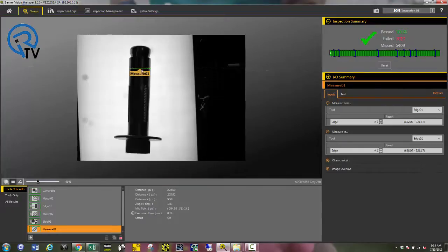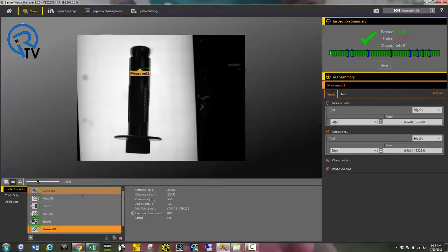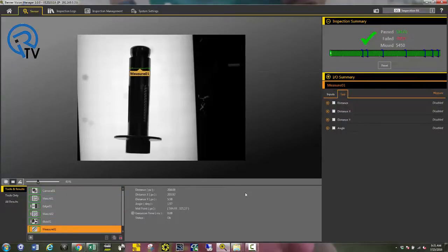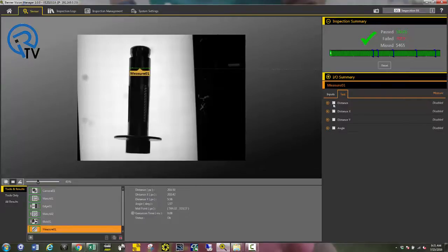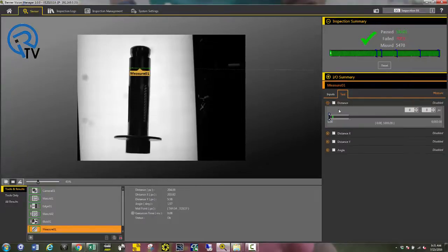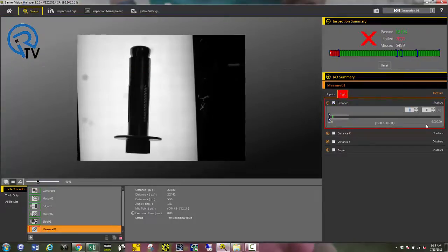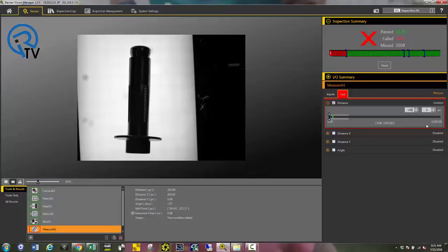Now I'm going to set up all my test tools to determine the pass or fail parameters of the inspection. Click test for each tool. As you can see, the overall diameter is 204 pixels. Select distance and give me a window. For this example, I'm going to use 190 up to right around 210.